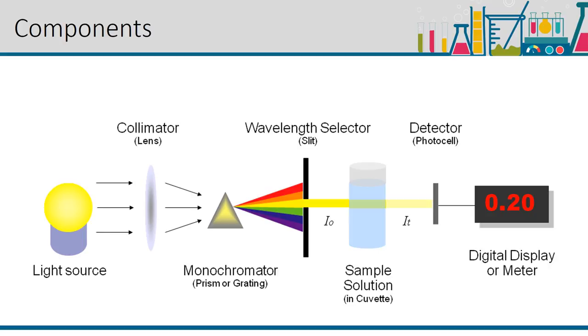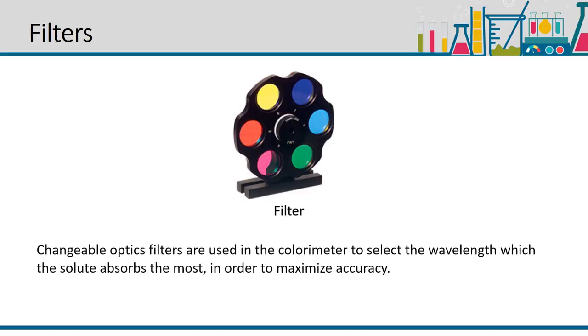To determine the concentration of an unknown sample, several sample solutions of a known concentration are first prepared and tested. The concentrations are then plotted on a graph against absorbance, thereby generating a calibration curve. The results of the unknown sample are compared to that of the known sample on the curve to measure the concentration.